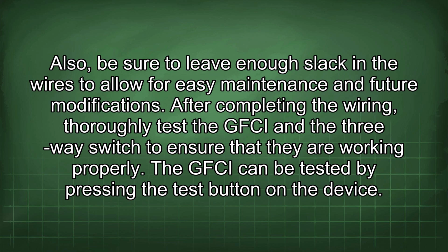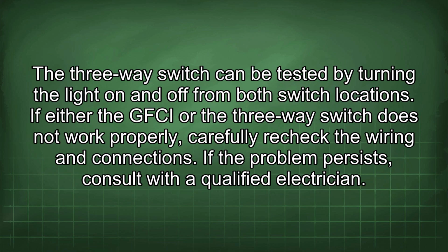After completing the wiring, thoroughly test the GFCI and the three-way switch to ensure that they are working properly. The GFCI can be tested by pressing the test button on the device. The three-way switch can be tested by turning the light on and off from both switch locations. If either the GFCI or the three-way switch does not work properly, carefully recheck the wiring and connections. If the problem persists, consult with a qualified electrician.